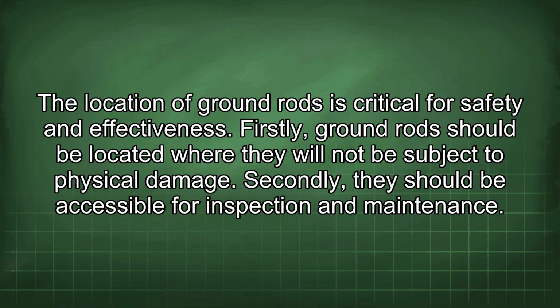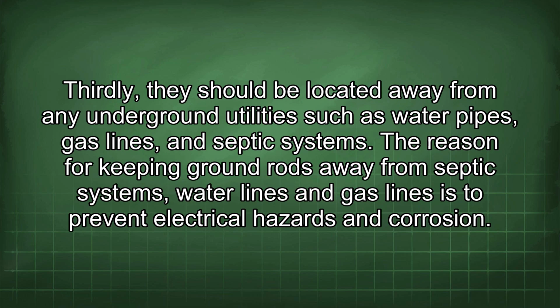The location of ground rods is critical for safety and effectiveness. Firstly, ground rods should be located where they will not be subject to physical damage. Secondly, they should be accessible for inspection and maintenance. Thirdly, they should be located away from any underground utilities such as water pipes, gas lines, and septic systems.